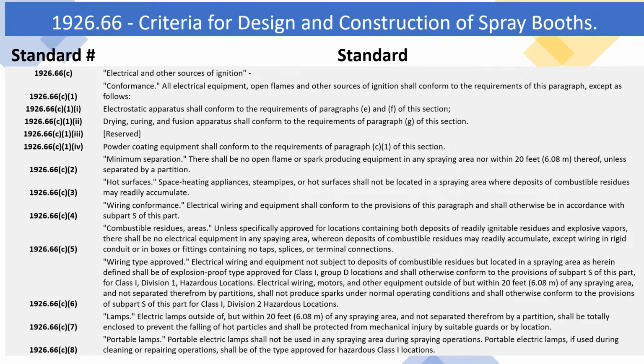1926.66(c)(5) Combustible residues, areas. Unless specifically approved for locations containing both deposits of readily ignitable residues and explosive vapors, there shall be no electrical equipment in any spraying area whereon deposits of combustible residues may readily accumulate, except wiring in rigid conduit or in boxes or fittings containing no taps, splices, or terminal connections. 1926.66(c)(6) Wiring type approved. Electrical wiring and equipment not subject to deposits of combustible residues but located in a spraying area as herein defined shall be of explosion-proof type approved for Class I, Group D locations and shall otherwise conform to the provisions of Subpart S of this part, for Class I, Division 1, hazardous locations.